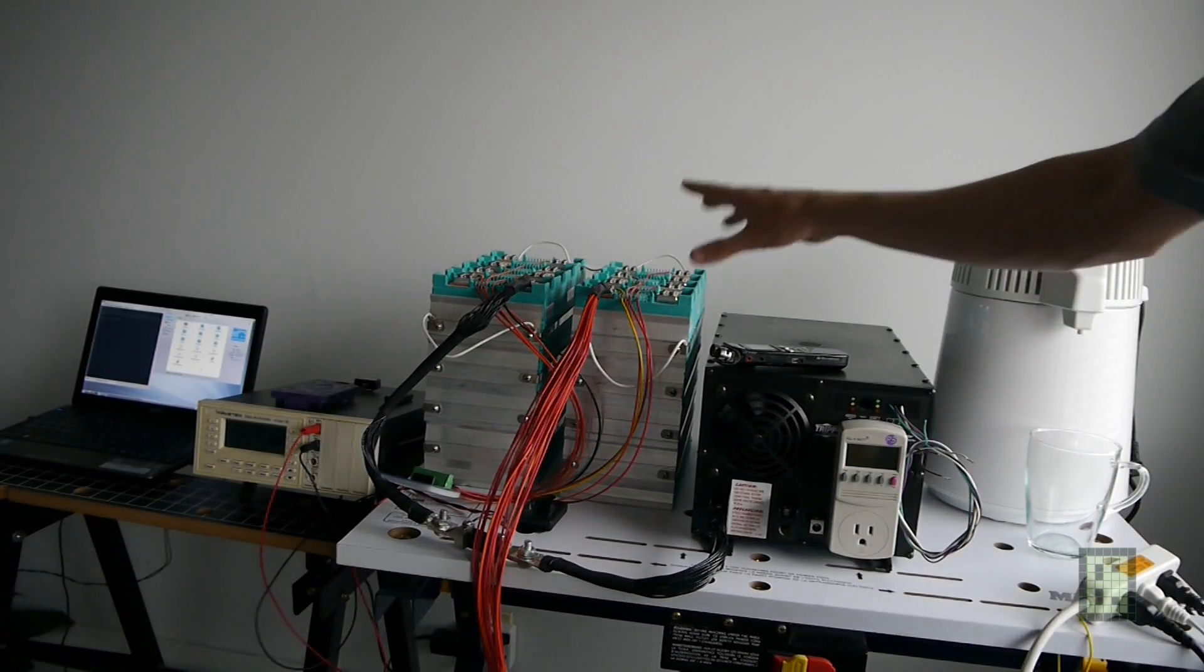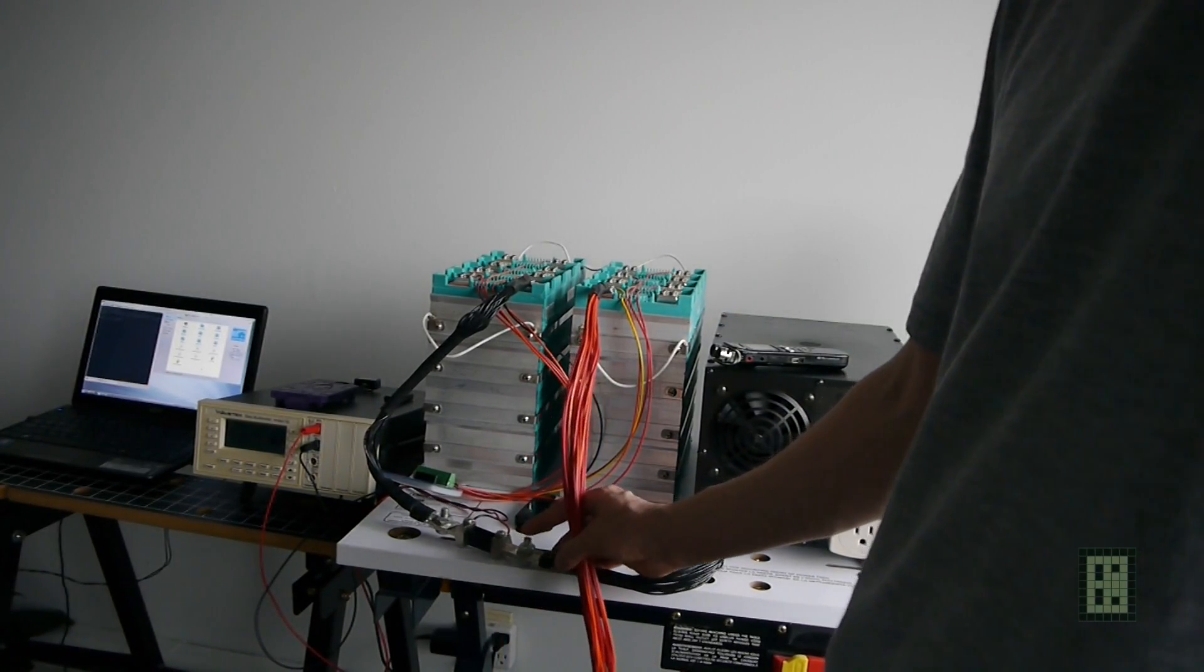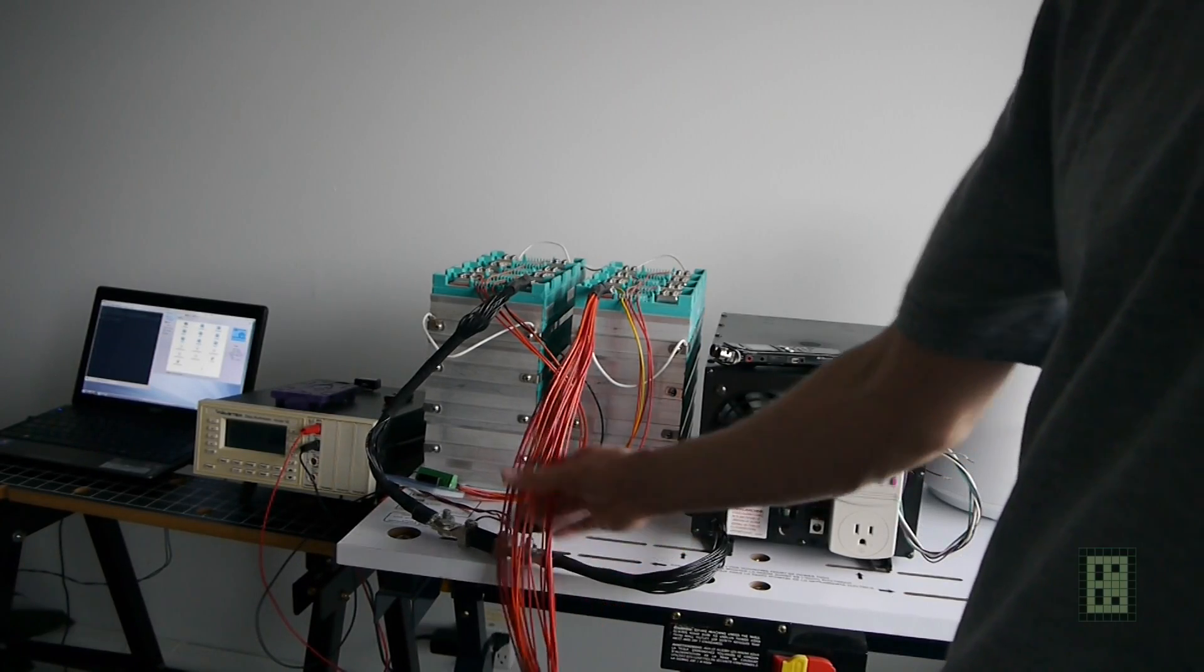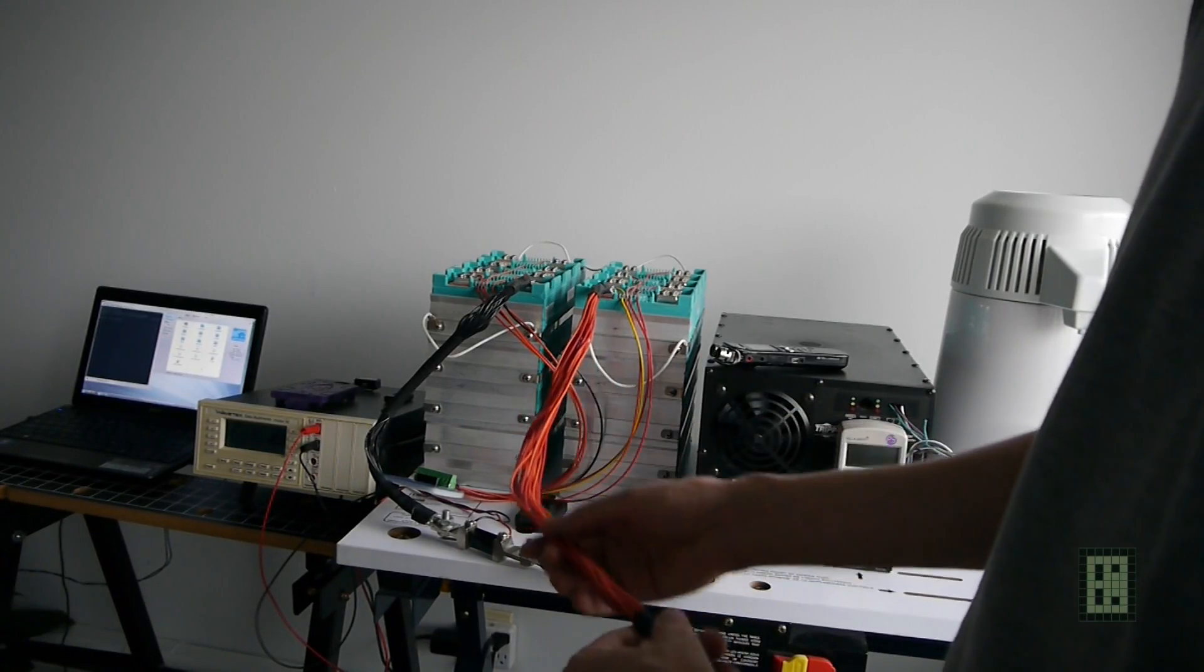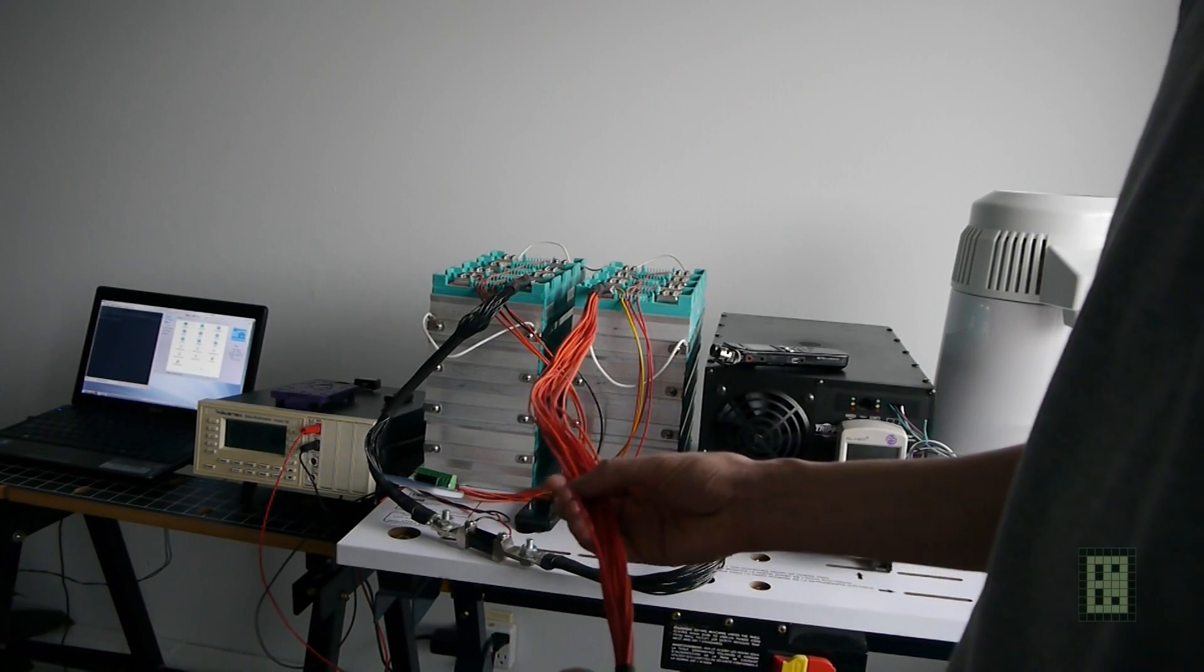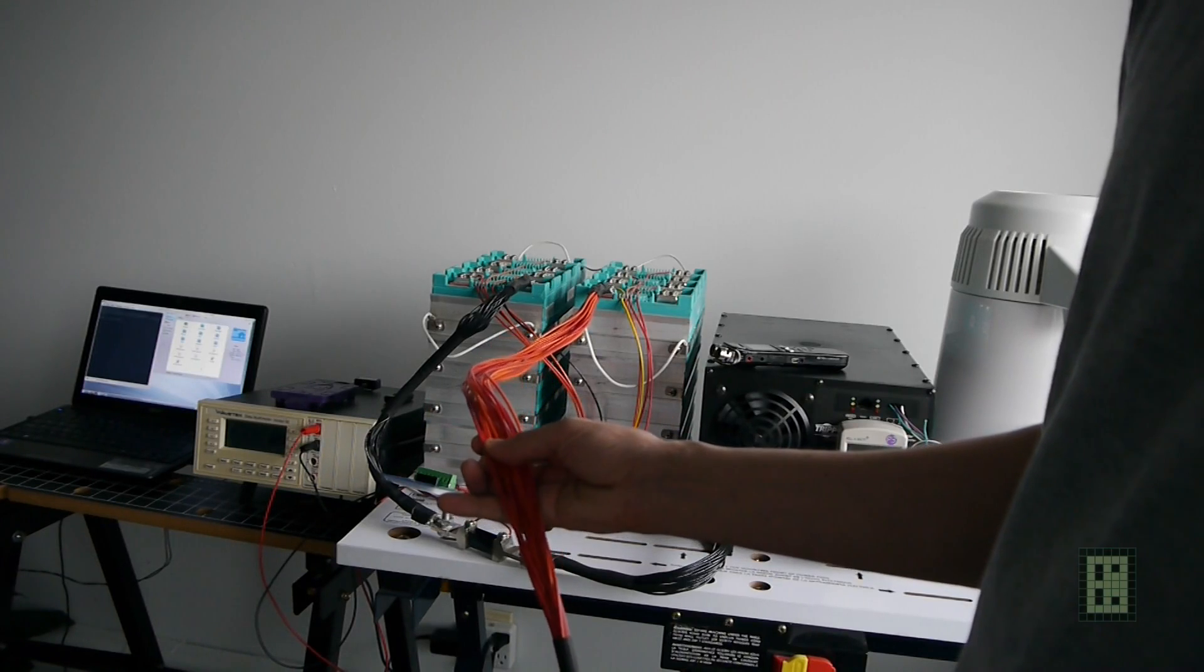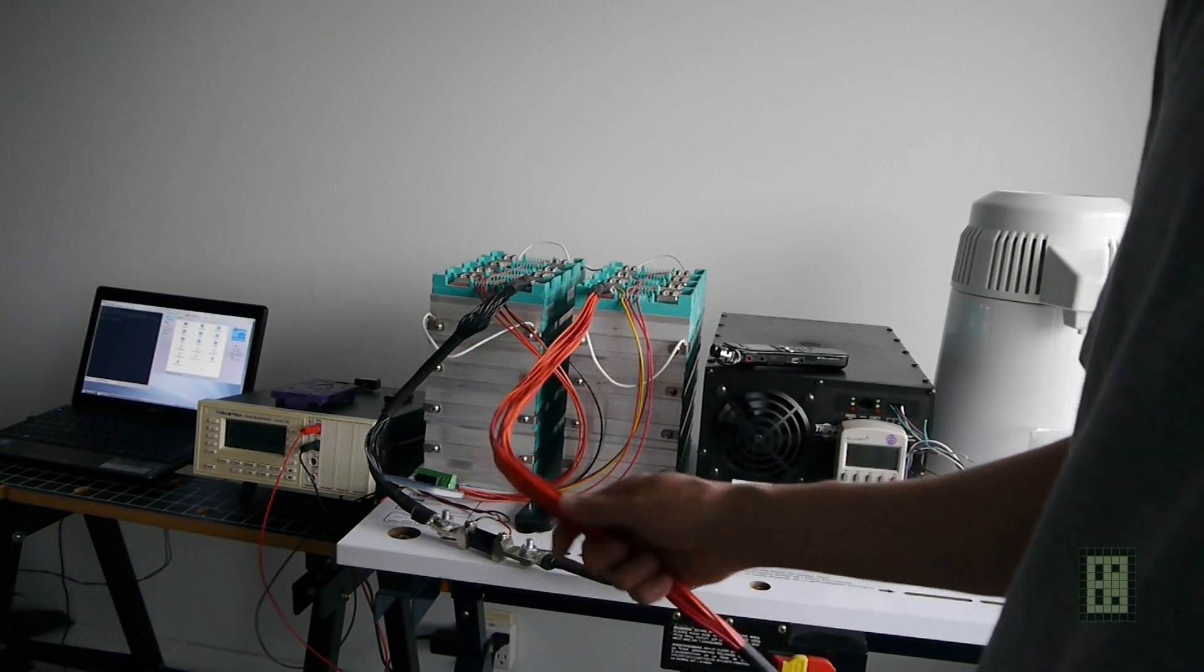Next is the shunt resistor. It's a 200 amp, 75 millivolt voltage drop on this one at 200 amps. The cables that I built are about 60 centimeters long, something like that, two feet. They use 0.8 to 0.9 square millimeter wires or number 18 imperial, and I have 20 of these for each cable.